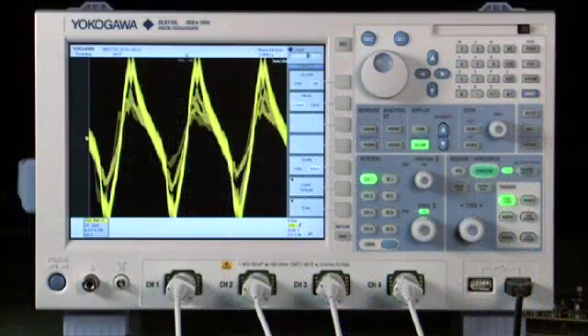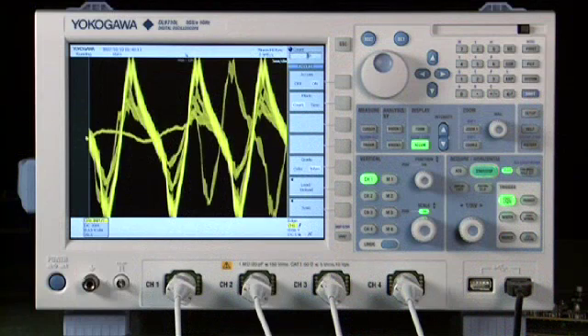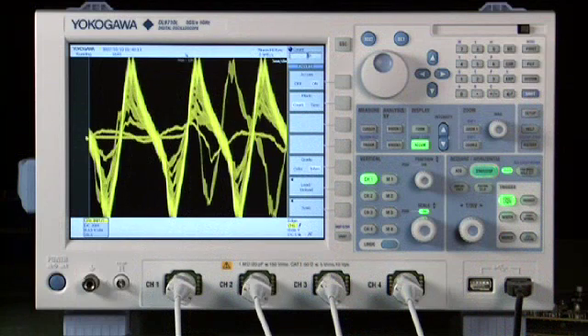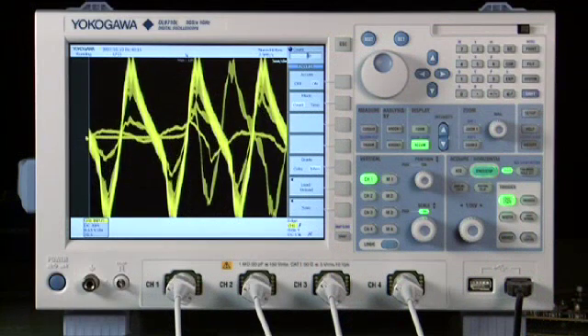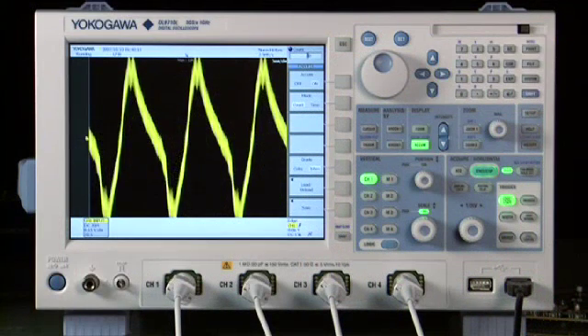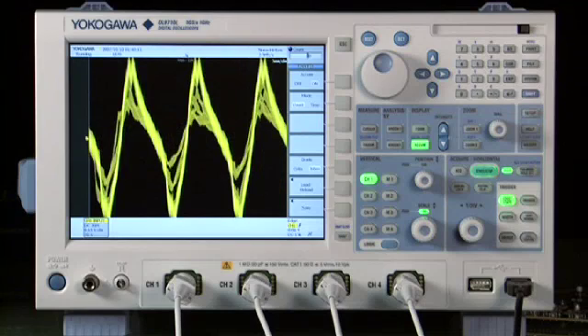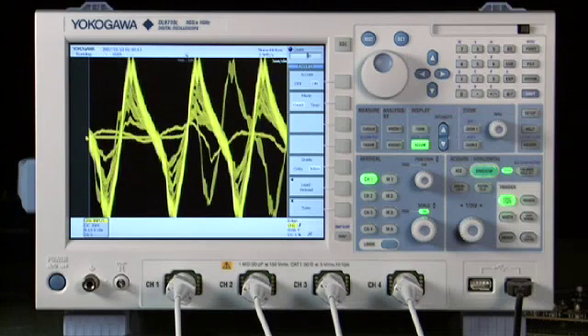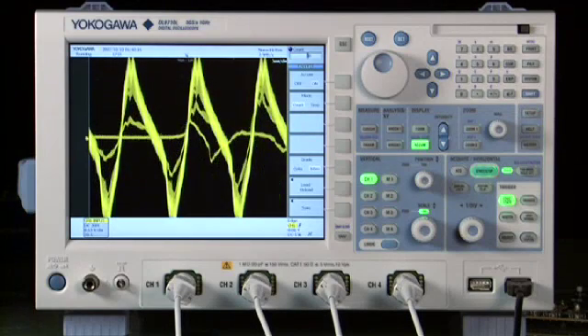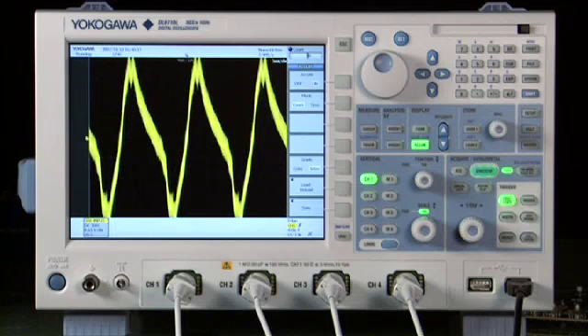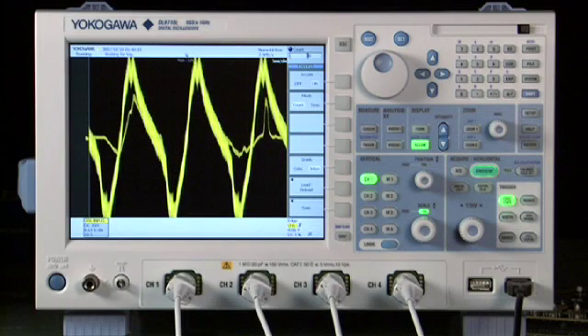Count-based persistence is an alternative method used to preserve waveforms which occur sporadically. Rather than fading out over time, the DL9000 will persist the most recent waveforms, even if there is a large time gap between triggers.